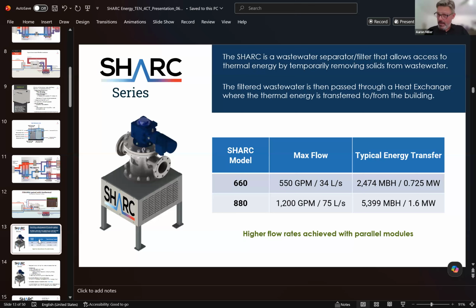One of the misnomers is that when people say heat recovery, they only think about taking energy out of the sewer. With these passive house design buildings and a lot of these net zero ready situations, and especially now with data centers needing cooling at massive capacity, heat rejection is going to be key, where we're able to reject heat from a cooling loop into another loop as opposed to evaporating it to atmosphere.